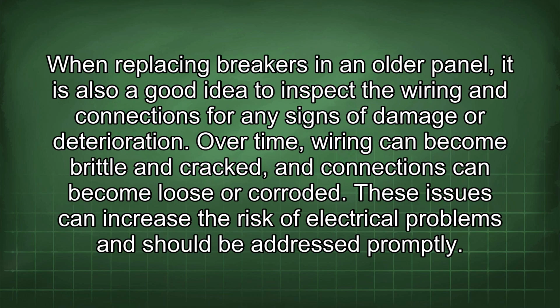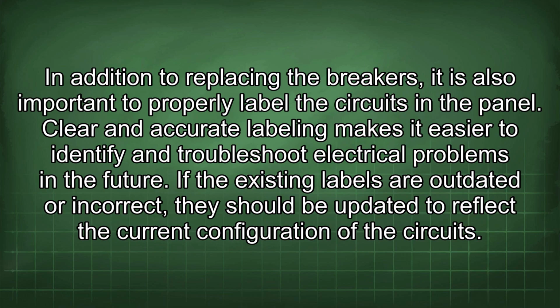When replacing breakers in an older panel, it is also a good idea to inspect the wiring and connections for any signs of damage or deterioration. Over time, wiring can become brittle and cracked, and connections can become loose or corroded. These issues can increase the risk of electrical problems and should be addressed promptly. In addition to replacing the breakers, it is also important to properly label the circuits in the panel. Clear and accurate labeling makes it easier to identify and troubleshoot electrical problems in the future.